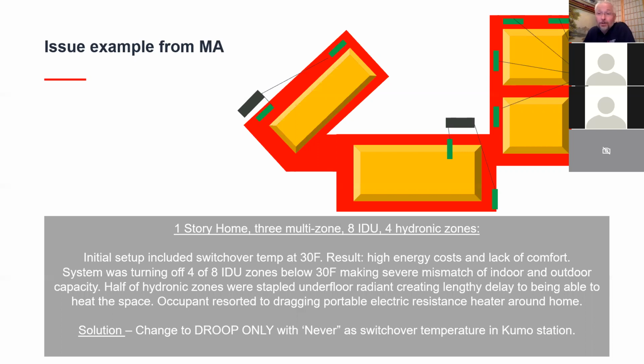So anytime it would drop below 30 degrees, the heat pump zones would shut off, the radiant would turn on, and the tenant would get very cold. In practice, the tenant would march around the house with a space heater and plug it in wherever she was hanging out. The consequence was that the heat pumps were cycling, using more electricity and being less efficient. She was adding a lot of electricity use by using a space heater anytime it was in the 20s or below. They were also using a fair amount of oil because of the cycling. The boiler would come up and maintain temperature and then shut off and try to heat zones. It was just all over the place. At the end of the year, the owner's like, I thought I was going to save a lot of money by putting in a heat pump system and getting as efficient as I can, but I actually spent way more in energy costs, and it wasn't able to work at cold temperatures.